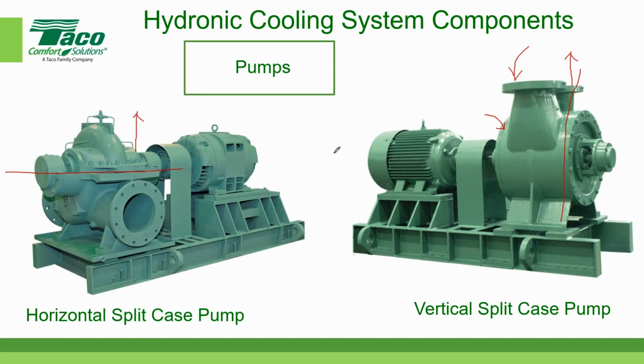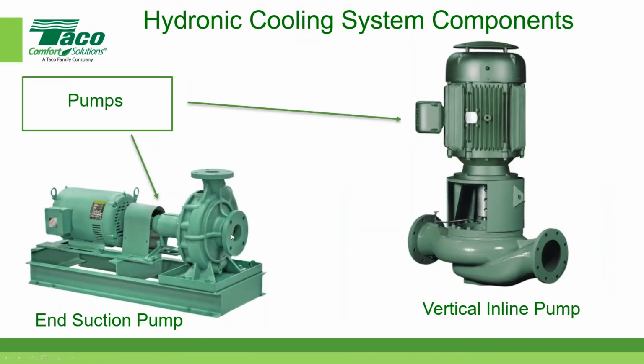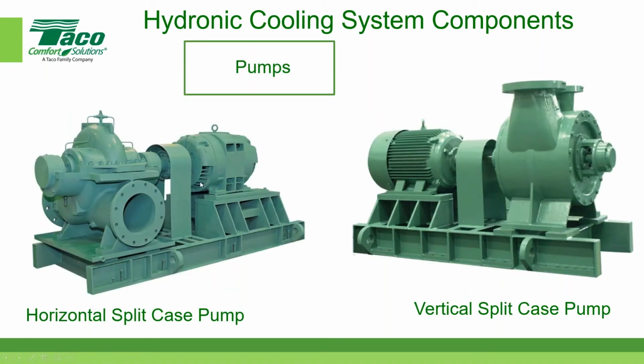So those four pumps are the most popular pumps that are used in our industry today. Actually, the previous slide, let me go back here. The previous slide is really the most popular pumps: the base mounted end suction and the vertical inlines. But for big systems, where you have to have lots of gallons per minute for both the chilled water and the condenser water, you start getting into the horizontal split case and the vertical split case. Okay, Brett, before I go on, any questions?